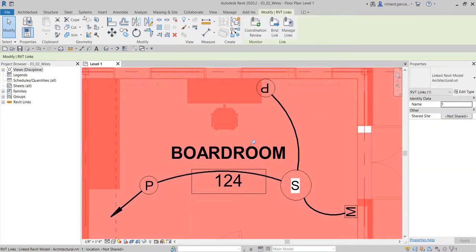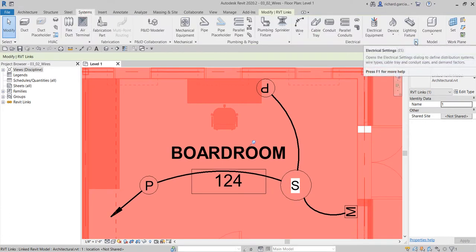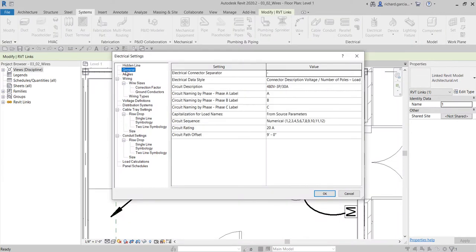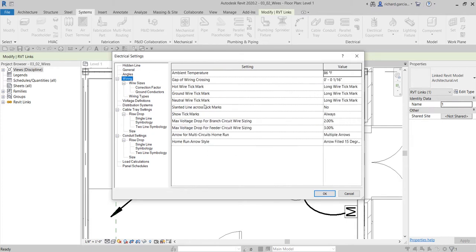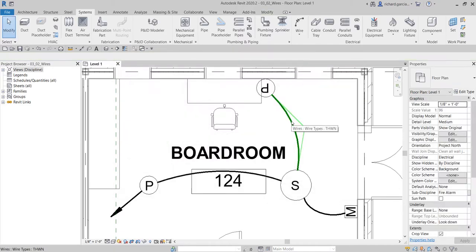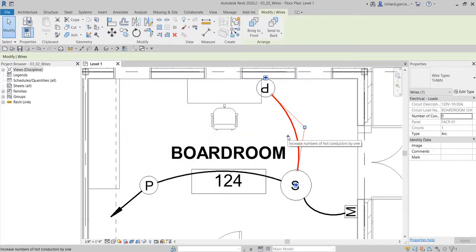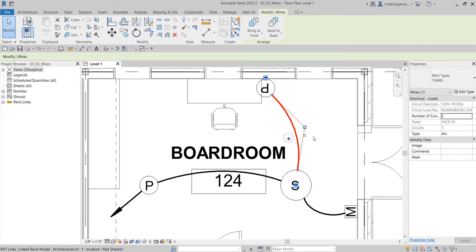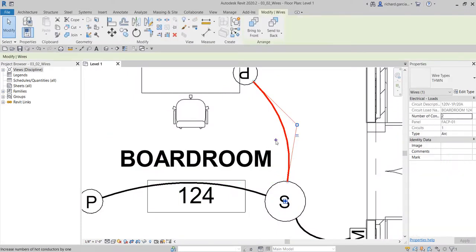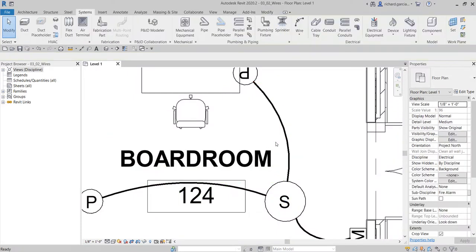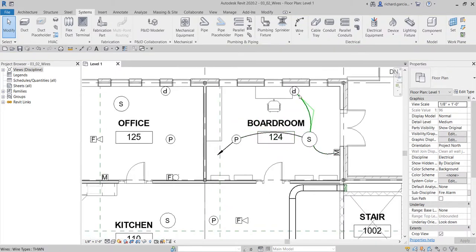Just as a review: if I go to Systems and then to Electrical Settings, you can set it under Wiring. You see 'Show Tick Marks' is set to 'Always' and the assigned tick mark is 'Long Wire Tick Mark.' I do not want to show the tick mark — I do not want to select that plus icon to show the tick marks. But just in case you want to show that, you just select the wire and click that plus to show the tick mark. That's how you create your wiring automatically.